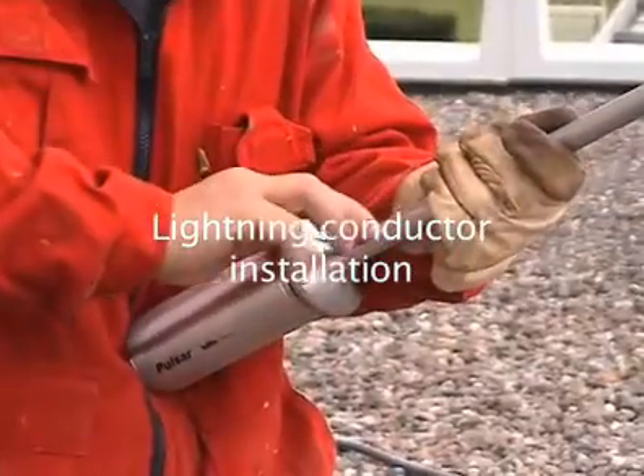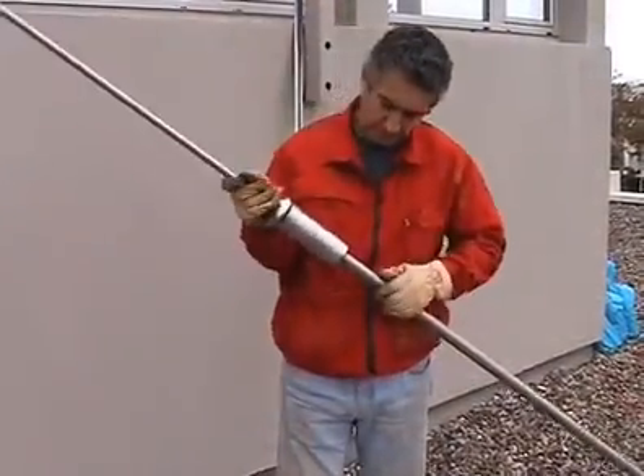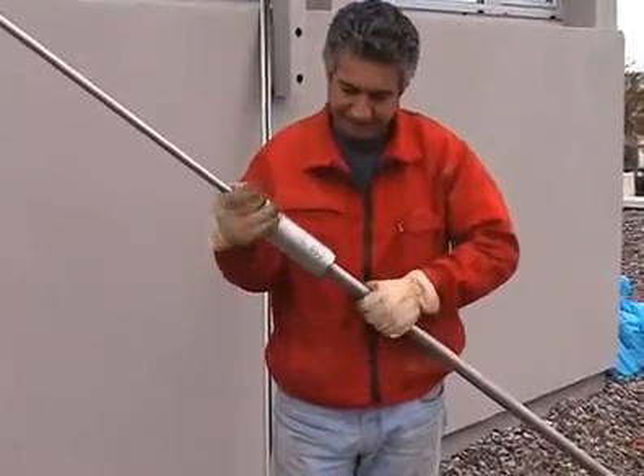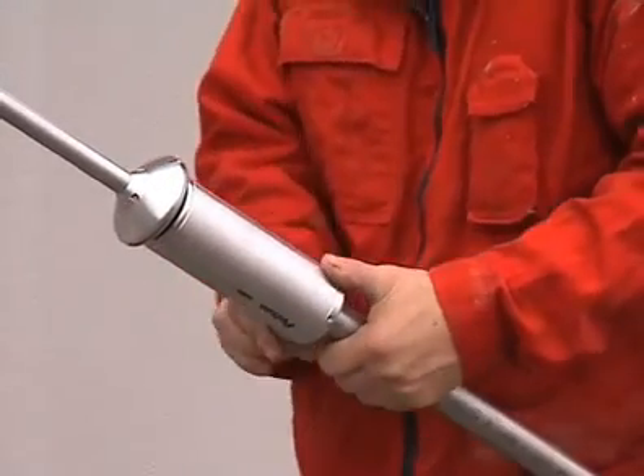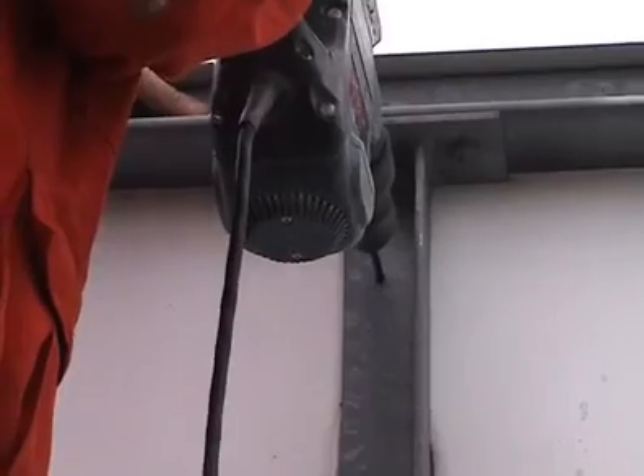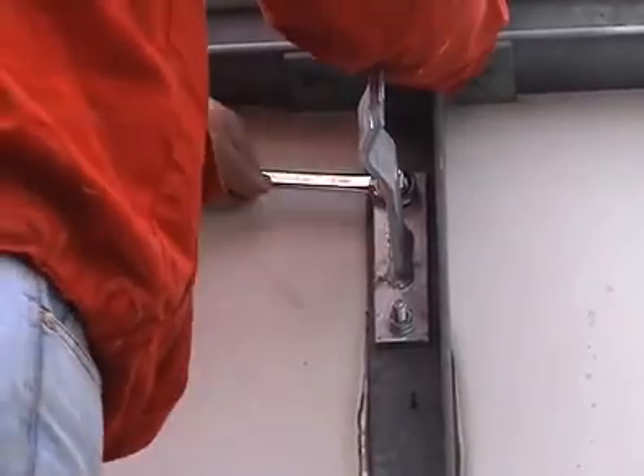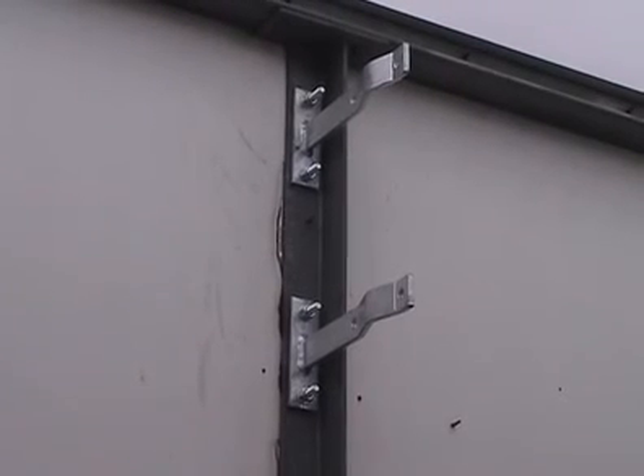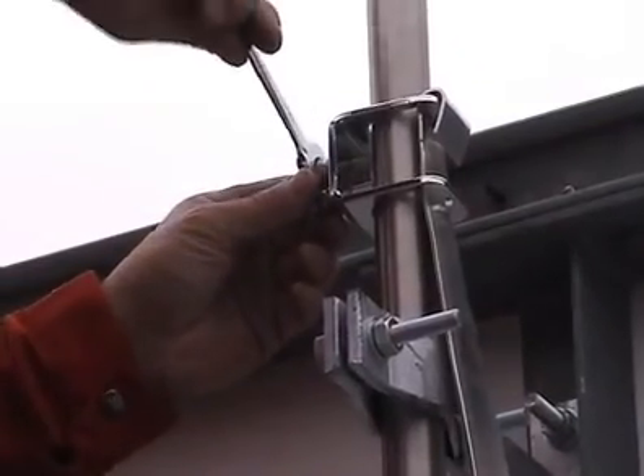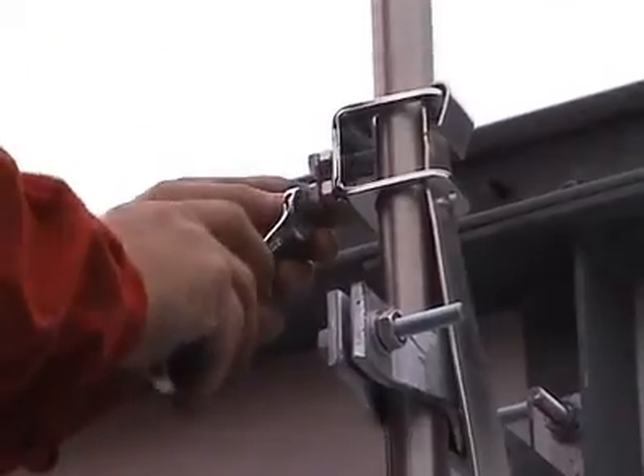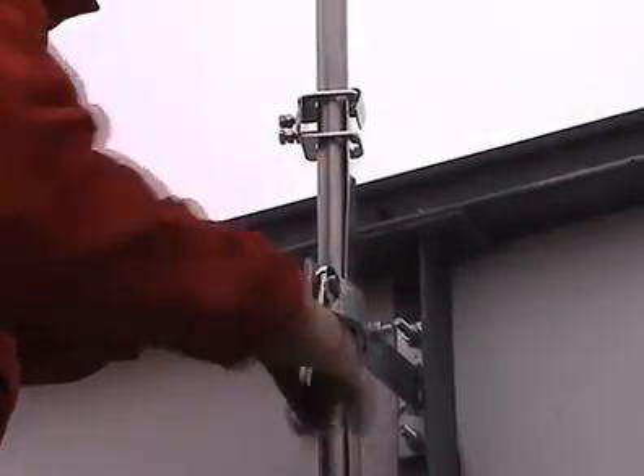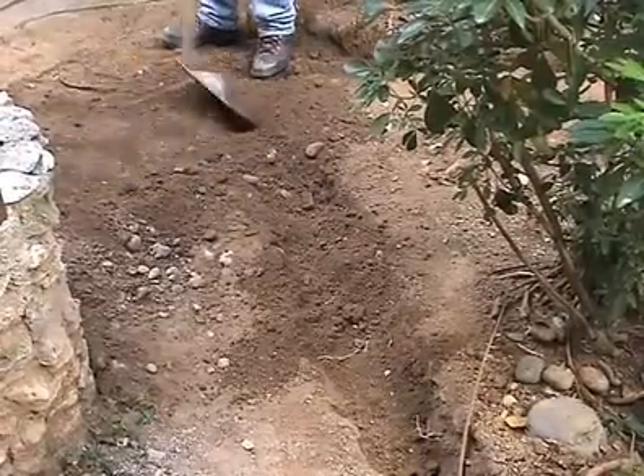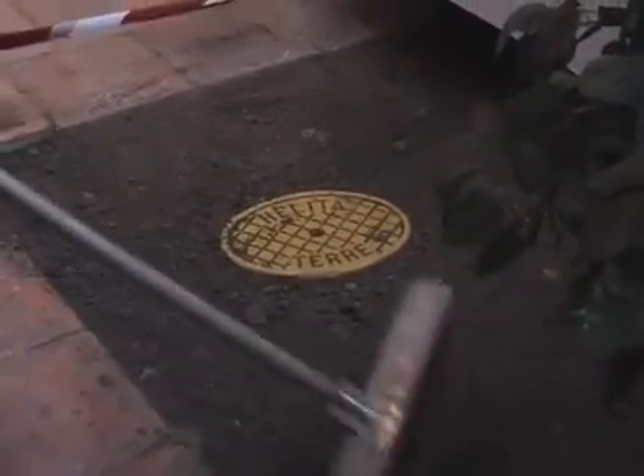Screw the tip into the pulsar's body. Screw the Pulsar's head onto the mast and tighten the screws. Mount the mounting brackets onto the wall. Attach the lightning conductor to the mounting bracket. Connect to the down conductor tape and complete the installation. Fill up the trenches. The lightning rod is now fully installed.